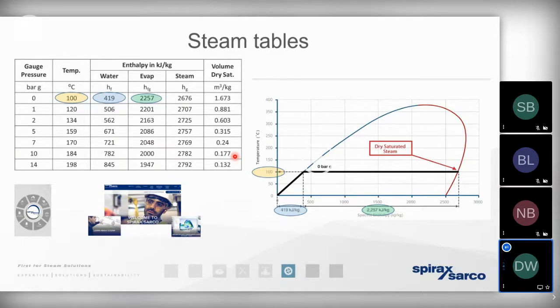So as you can see, at a higher pressure, we've really compressed that volume of steam down. So it occupies a much smaller volume. And that's one of the reasons why a high pressure steam can be distributed in a very small pipe diameter. So as you can see, if we manipulate the pressure of the steam, all of these values are changing. So that's one of the important reasons why we encourage you to download that useful little app that's demonstrated in the bottom left corner of the screen.